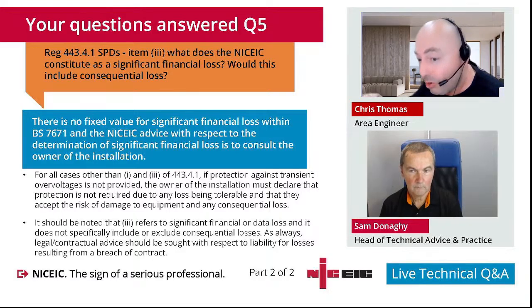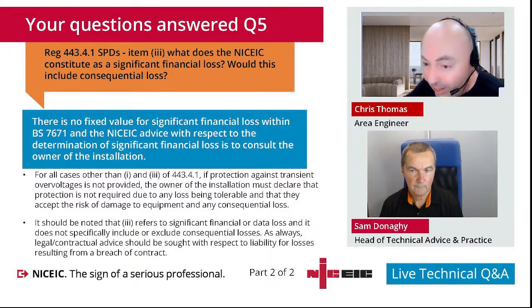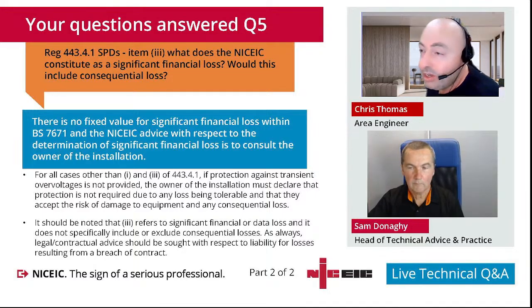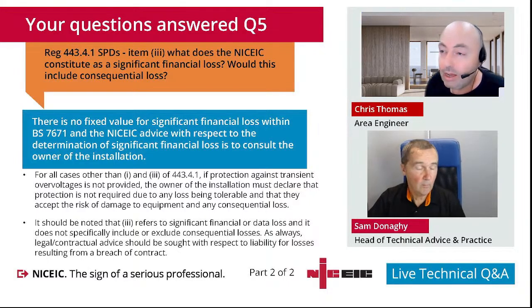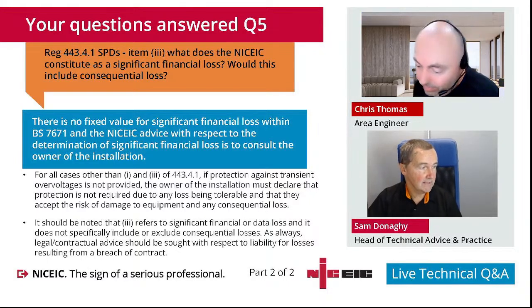So even if you've not got a clue where to start looking, I always find Appendix 15 really useful, and it'll then lead you to the more technical requirements like sizing an adequate protective device, sizing the cable, and obviously making sure the system's fit for purpose. Yeah.